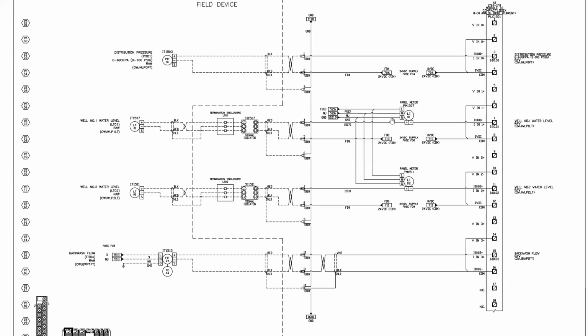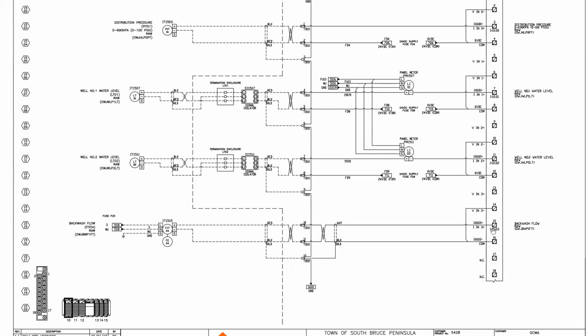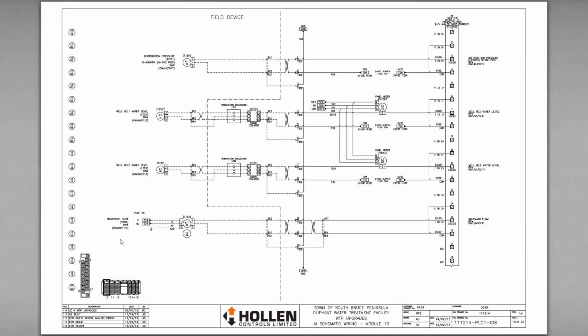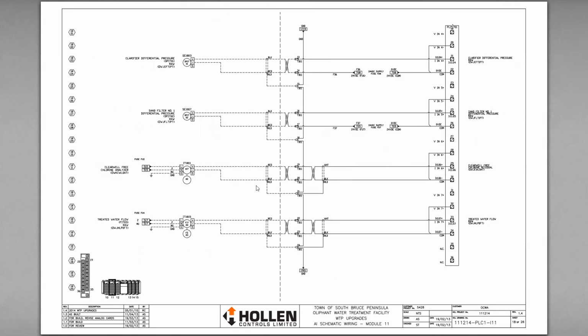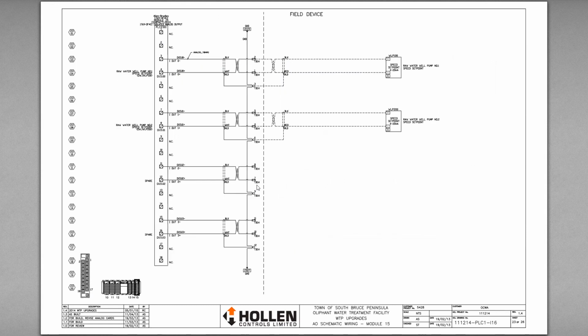This level looks like it's receiving power from 526 on fuse 13. It provides power to the panel meters. These are 4 to 20 milliamp water levels. Backwash flow. This instrument's provided power by FU5. So I'm gonna switch to a different drawing set. I think you guys have got this, unless you have questions about this drawing set. I'm gonna switch to a different one. Okay.